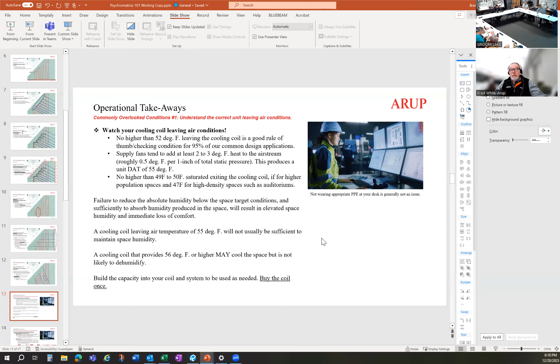So we cool it down to 52, we get free reheat. We put it into the space at about 55 degrees. And that's what most people find reasonably comfortable for typical air conditioning. I'm talking about comfort air conditioning, not particular processes. But it's important you buy the coil once, make sure the capacity is built into that coil. There aren't a whole lot of things you can do once the coil's built and installed. You're pretty well done.